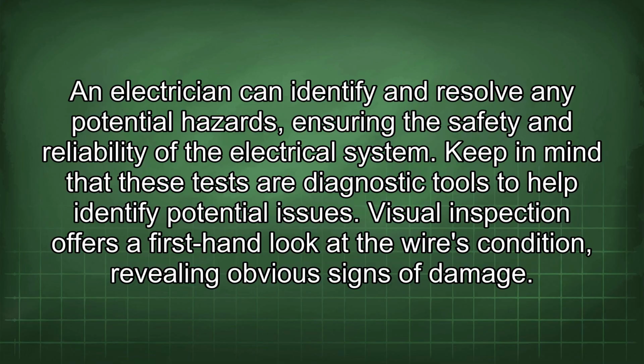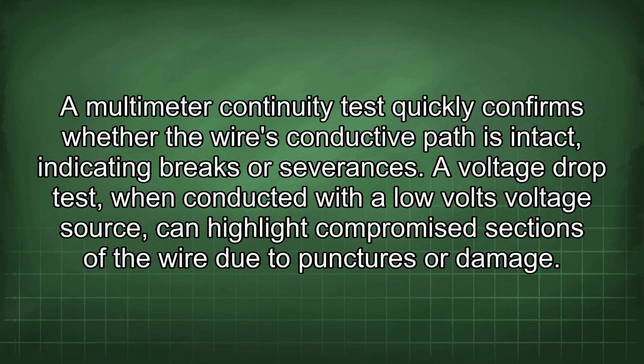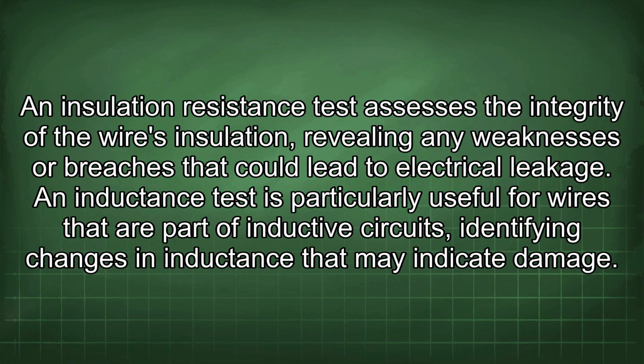Keep in mind that these tests are diagnostic tools to help identify potential issues. Visual inspection offers a first-hand look at the wire's condition, revealing obvious signs of damage. A multimeter continuity test quickly confirms whether the wire's conductive path is intact, indicating breaks or severances. A voltage drop test, when conducted with a low voltage source, can highlight compromised sections of the wire due to punctures or damage. An insulation resistance test assesses the integrity of the wire's insulation, revealing any weaknesses or breaches that could lead to electrical leakage.